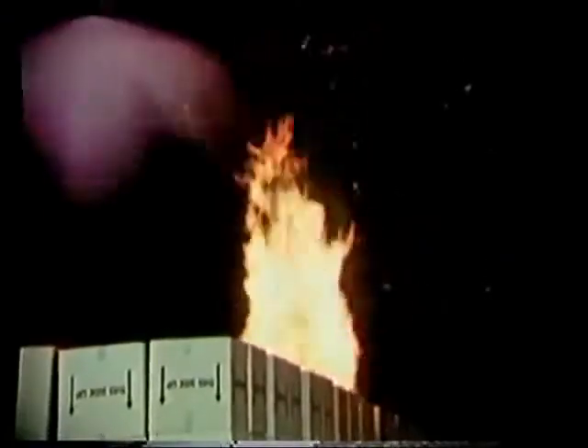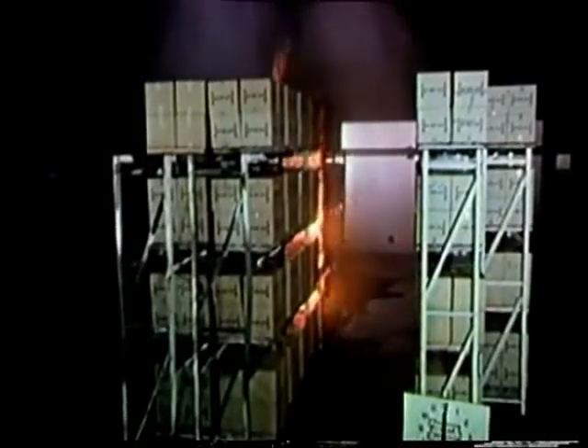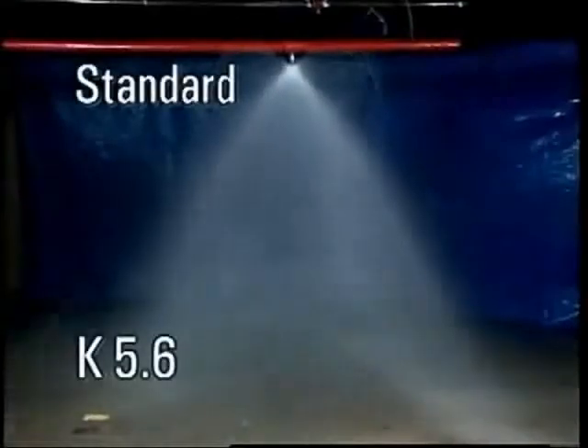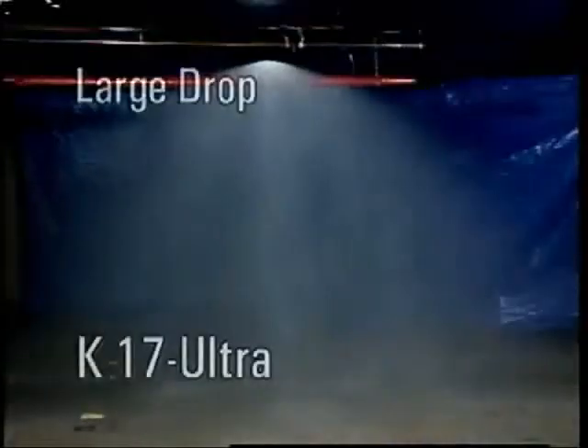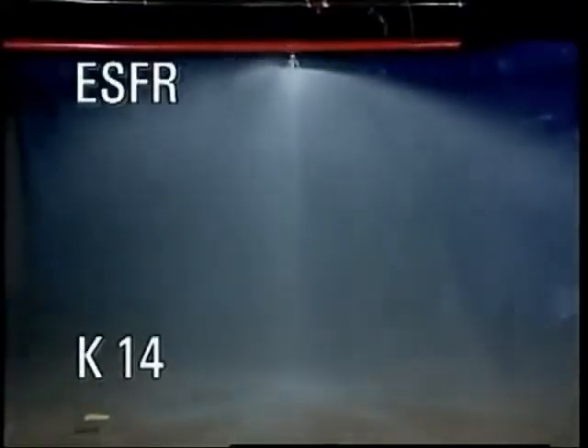An essential factor in proper sprinkler operation is an adequate flow of water. At the same time, we do not want too many sprinklers to operate, as too much water discharging can overtax our supply or cause needless water damage. The sprinkler's density is described as the amount of water released over a specific floor area. It is usually expressed as gallons per minute per square foot. Density is a function of pressure and orifice size. Depending on the occupancy, more or less cooling water may be needed.